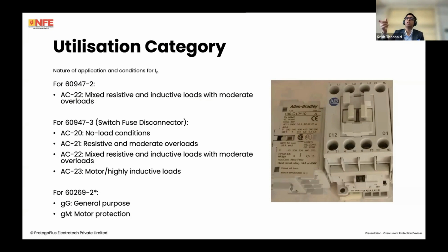When it comes to the actual switch fuse disconnector or an isolator, there are four categories. There are switching, so you turn on and off under no load conditions. Frankly, that we see are rare. That is only the main switch on a domestic distribution board. You'll only turn it on and off under no load conditions.